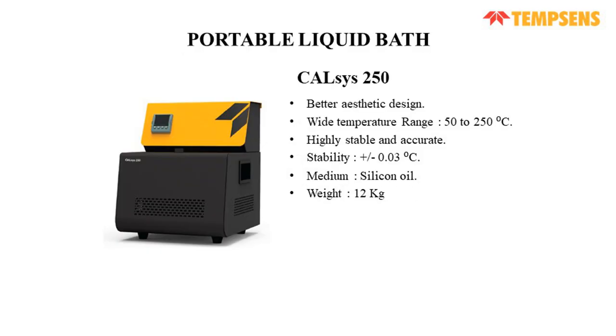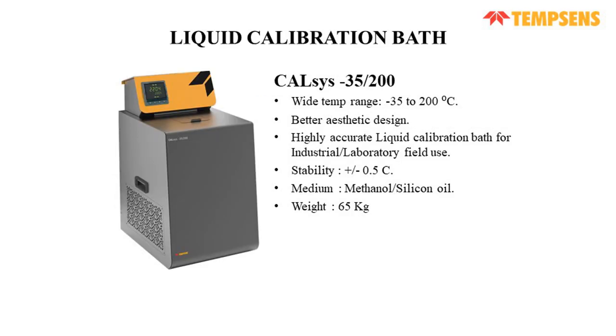So this is the portable liquid bath. It is the CALsys 250, and the temperature range is 50 to 250 degrees. It has a very aesthetic design and is very lightweight to carry for on-field applications. The medium for this is silicon oil, as I discussed before, and the stability is plus minus 0.03 for this model. Now we have the CALsys-35/200, and the range is minus 35 to 200 degrees centigrade, and the stability for this model is plus minus 0.5 degrees. For low temperatures we use methanol as the cooling medium, and for high temperatures we use silicon oil, and the weight of this calibrator is 65 kgs.